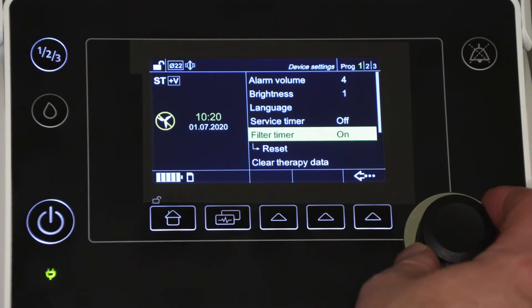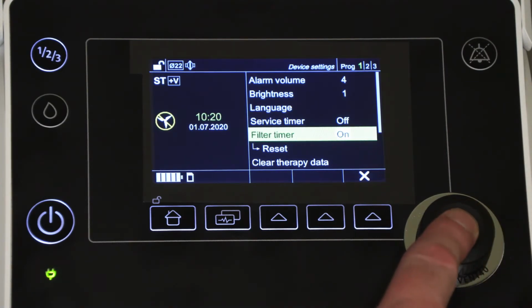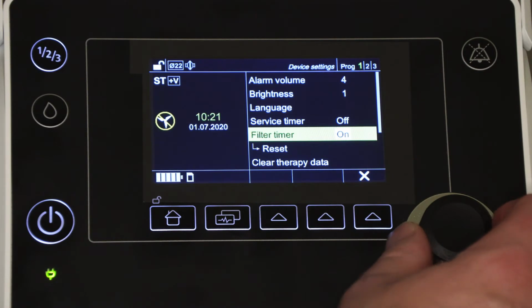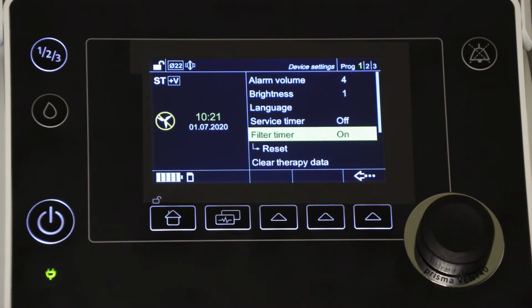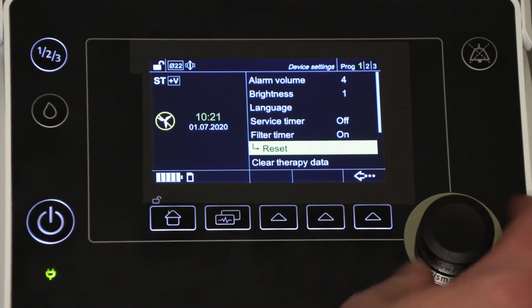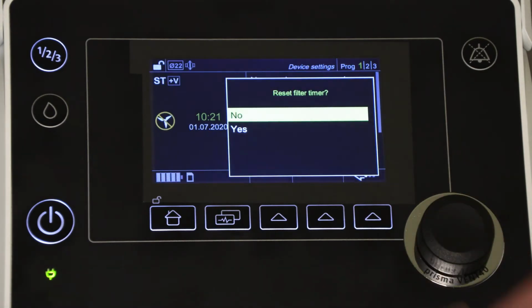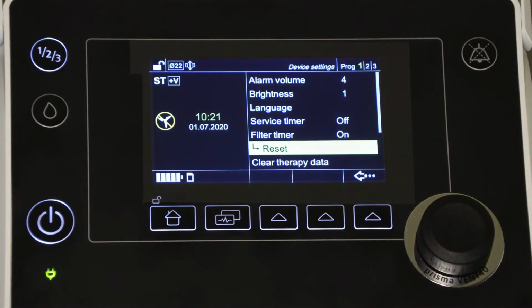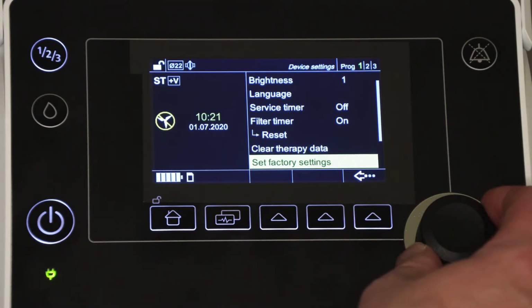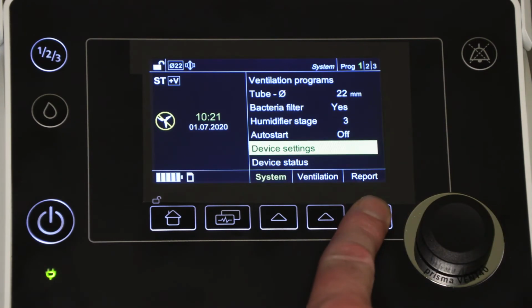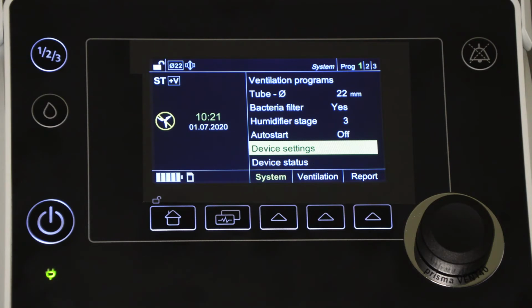The filter timer can simply be set to on if it's preferred to have a reminder of when the air filters are due to be changed. If this setting is activated, you'll need to reset it when the filters are changed. You can clear therapy data if the ventilator is being taken from one patient and given to another. And you can reset to factory settings, which shouldn't be necessary. Press the back button to get back to the system menu.